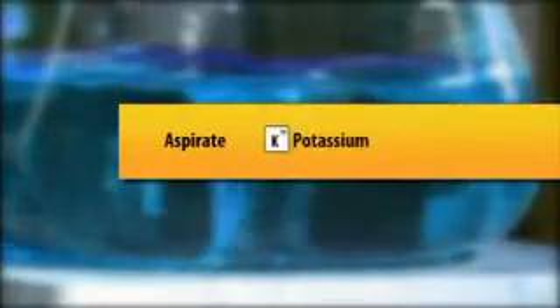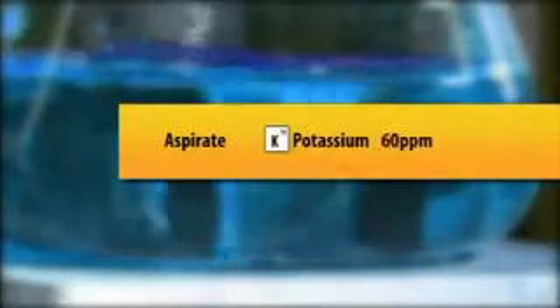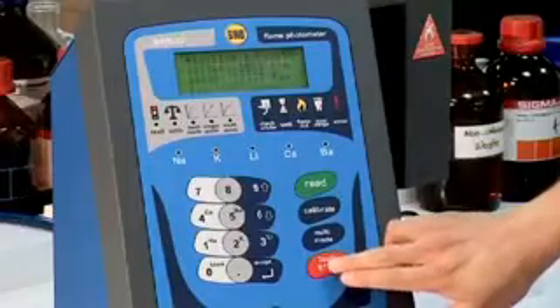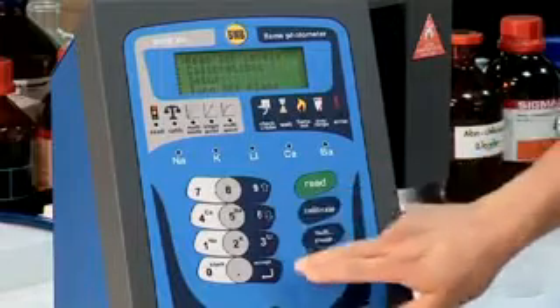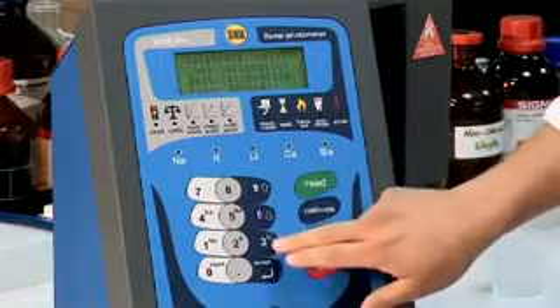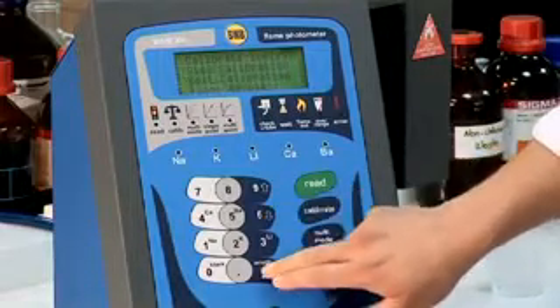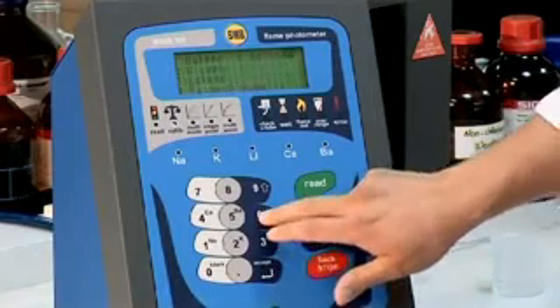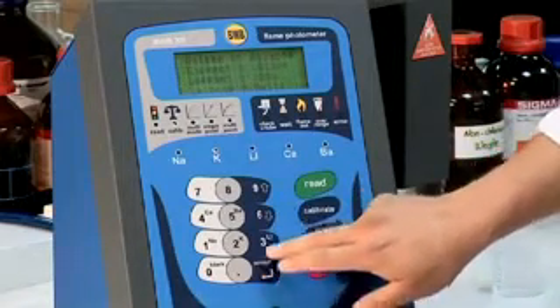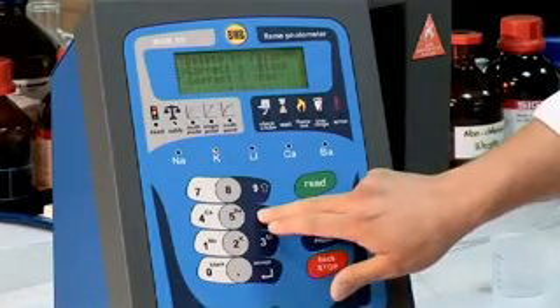The second icon represents the noise in the system. A full black rectangle means that there is a lot of noise. A single dot means that there is very little noise. When a sample is first introduced, the icon will change to completely black and will gradually reduce to a single dot. A reading should only be taken when the icon shows a single dot.